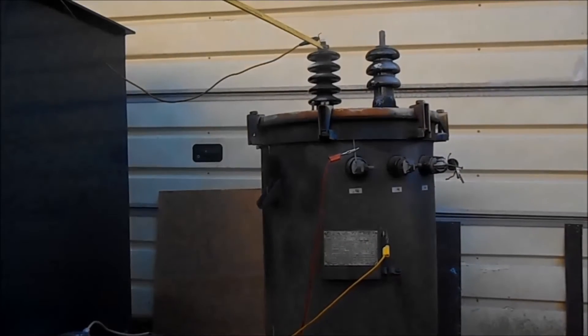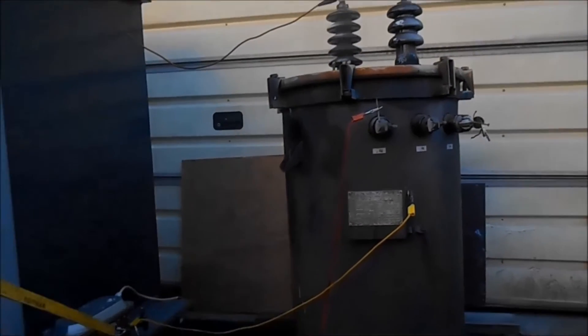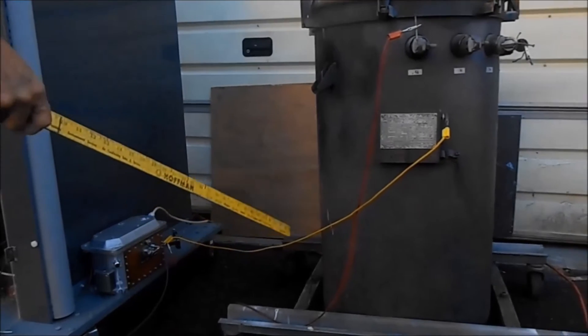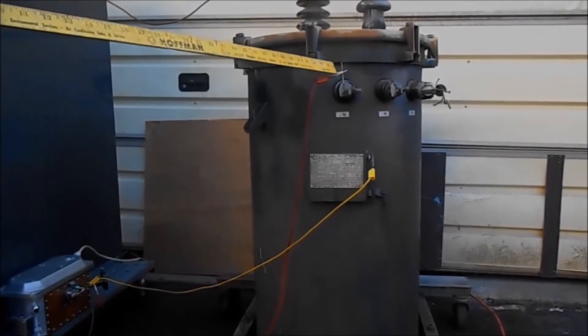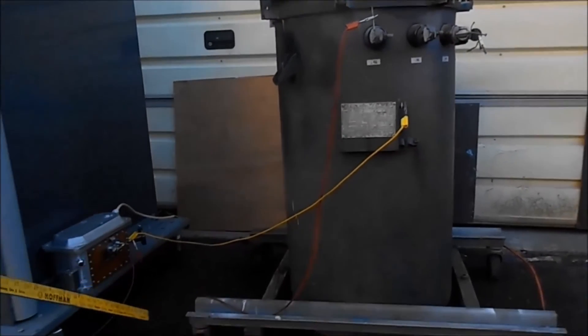We have to hook up the high voltage to the bushing. The return connects to the shunt and the ground wire connects it to the impulse generator base.